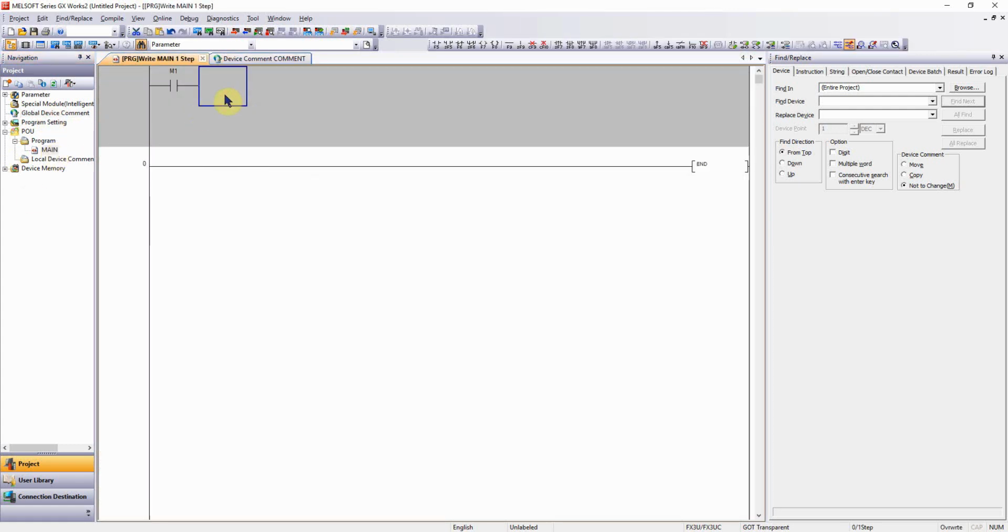But a D word is only going to show you the first of those double word references. So, like I said, if I'm doing a D word integer and I'm starting at D0, if I search for D1, it's not going to show up in my program at all, but it's most certainly being referenced if it's being used in a DADD or similar instruction.